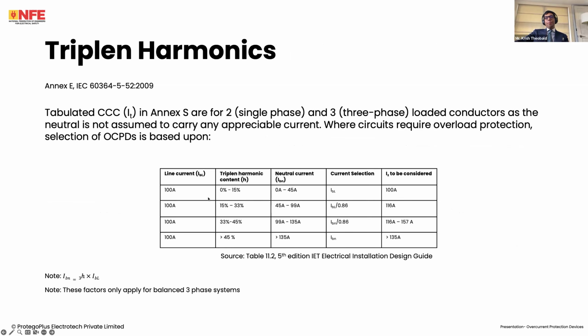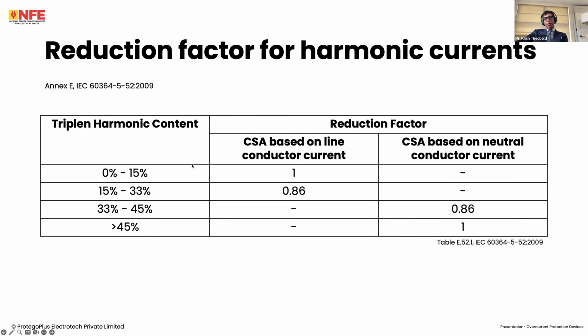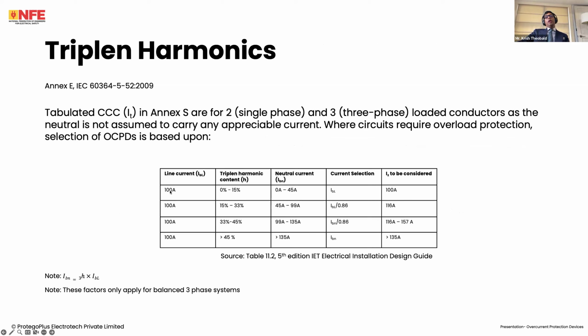This is just an example calculation for the previous table. If we consider 100 amp current in the line conductor and 15% triplen harmonic current, that is basically times 3, 45 amps flowing in the neutral. We decide the current on the basis of the line conductor. Consider only 100 amps. If it is between 15 to 33%, and we consider 33%, 33% times 3 times 100 is 99 amps. We do 99 divided by 0.86.